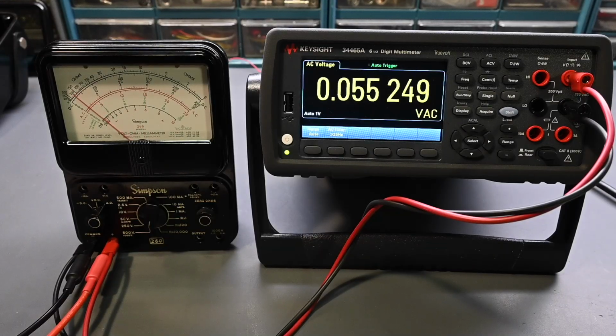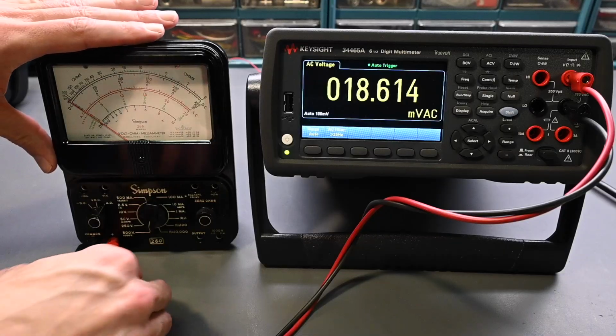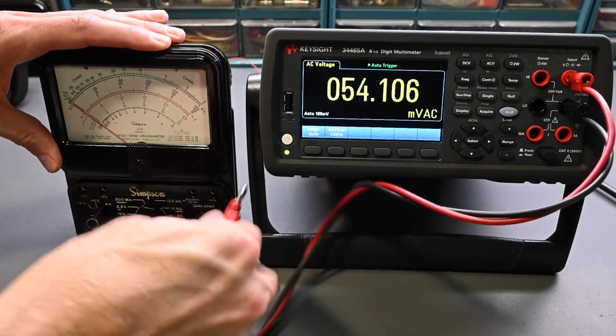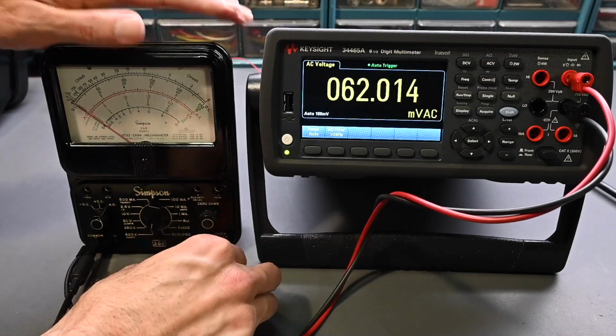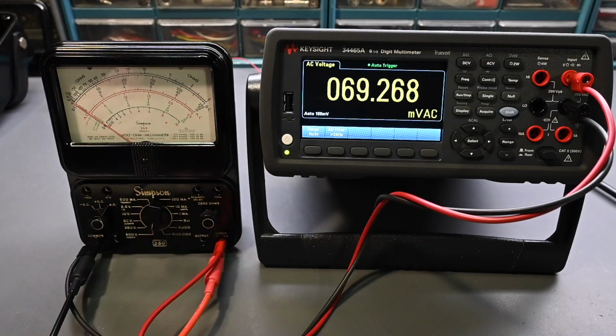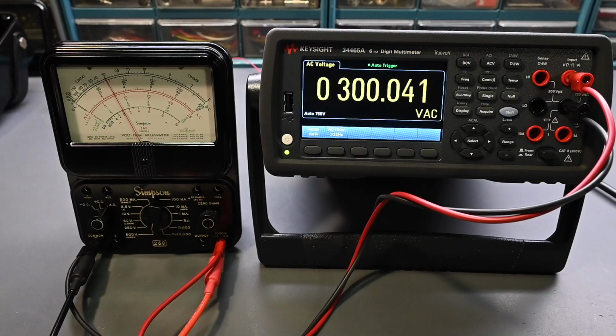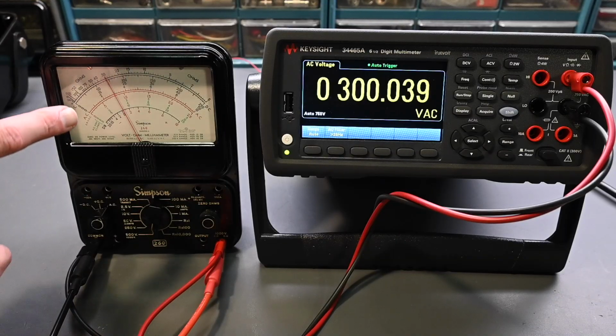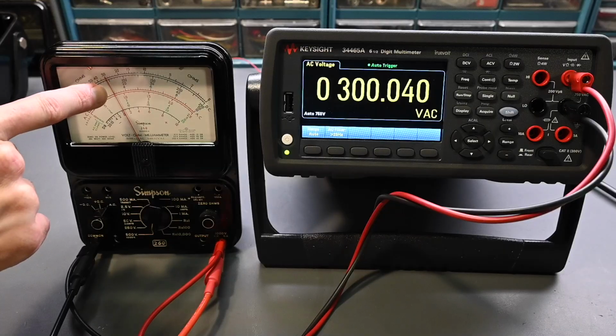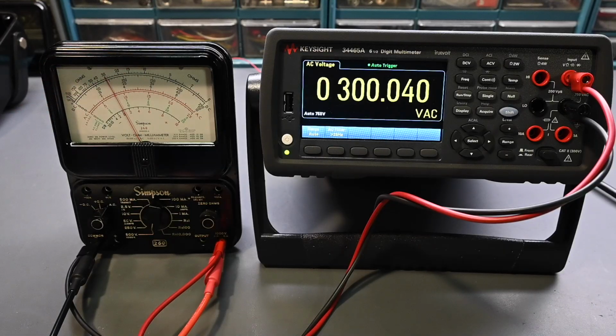Now let me turn this off, and I'll go to that other highest voltage range, turn that off. Move that over there. So the 1000 volt range. Turn this back on. Still 300 volts. And how does that look? That's 1000, 300. Yes, that's spot on. Perfect. Right there, that's right on the tick mark. So excellent. Accuracy is looking very, very good. I'll double check the AC calibrations here a second time on the 250 volts and the 2.5 volts, and then I'll put the meter back together.